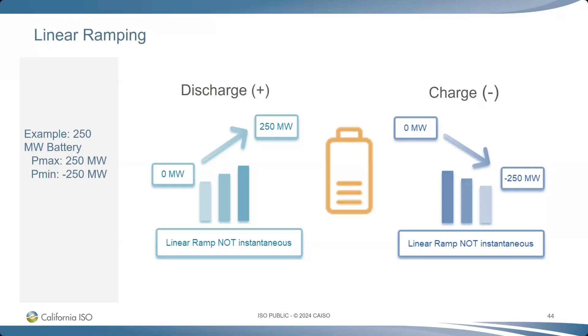Brad, before we go on, I see you have a hand up. Yeah, I do. One thing I was going to ask: is there any specificity when we say what we want for ramp rates? We say make it linear, which I agree with, but do we want to say 100 megawatts a minute, 1,000 megawatts a minute? Is there any guidance or limitations that would be hard and fast numbers? Because the systems can do on the order of thousands of megawatts a minute if we went to an instantaneous setting.